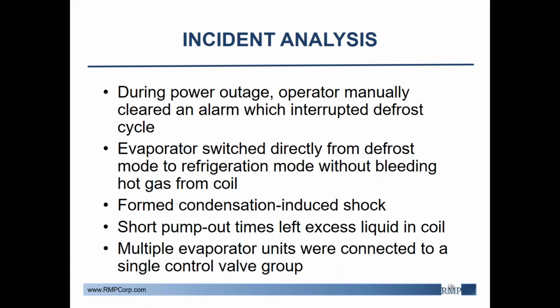Hot gas and low-temperature liquid mixed in the pipe, which caused the gas to quickly condense into a liquid, forming condensation-induced shock.